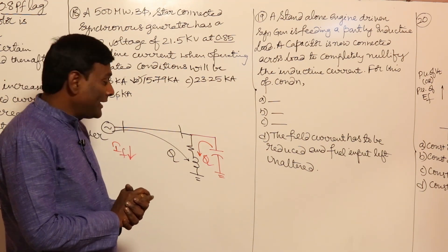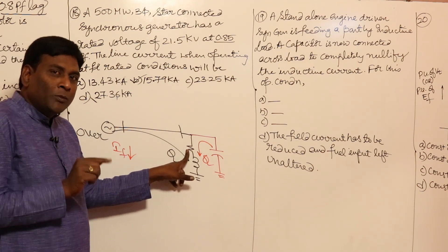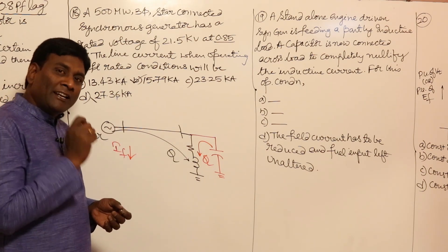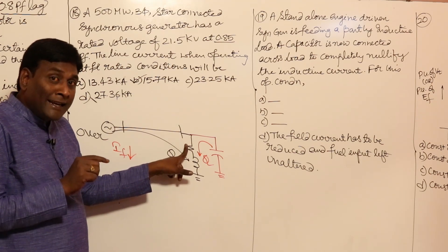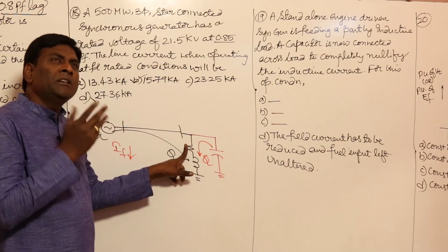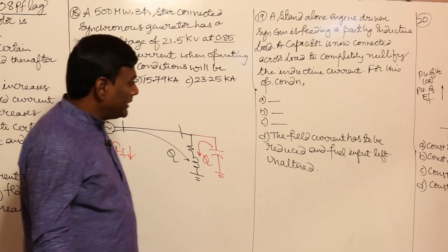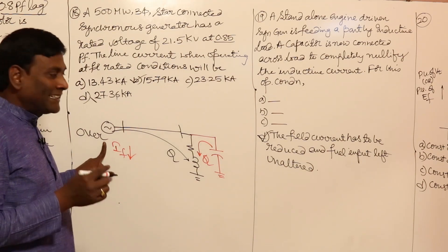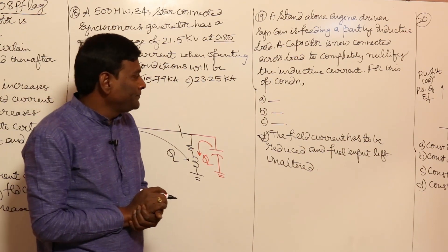Field current has to be reduced from over-excitation to normal excitation. What about fuel input? It should remain unchanged, because the active power requirement of the resistive part of the load is the same. Reactive power can be delivered by anybody, but active power must be delivered by the generator only. So the answer is: field current is reduced and fuel input is left unaltered.